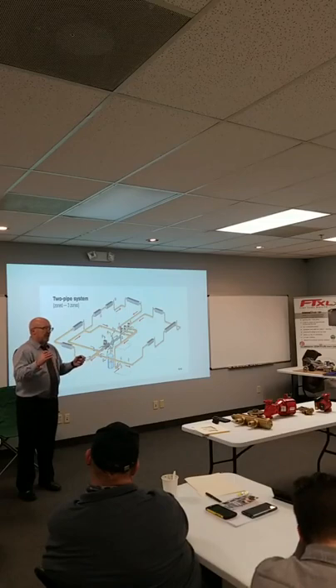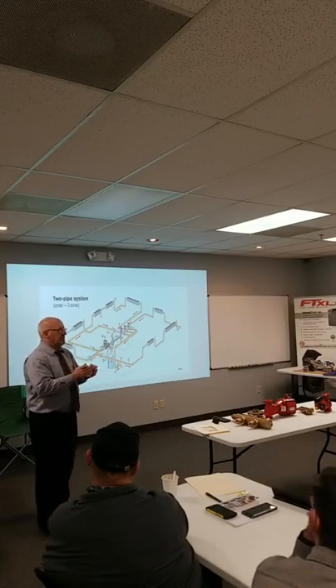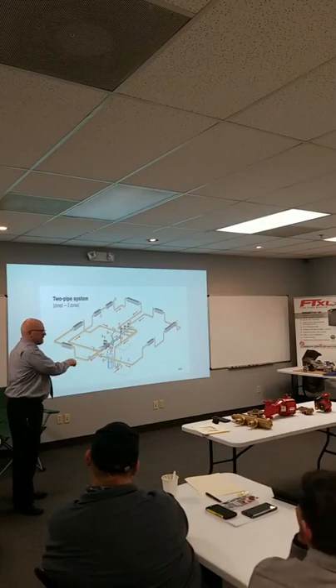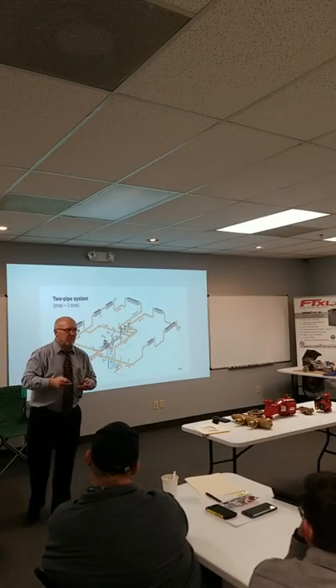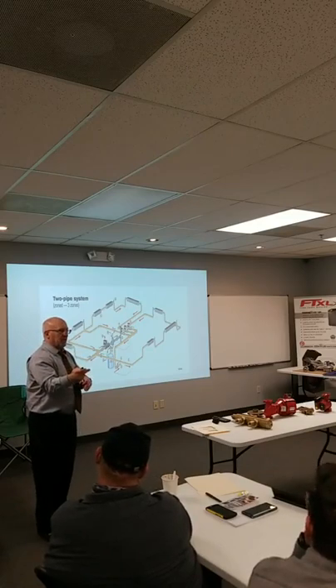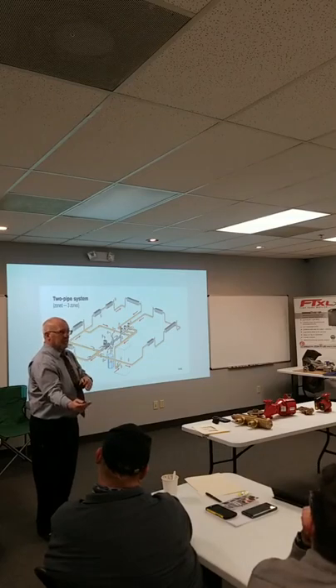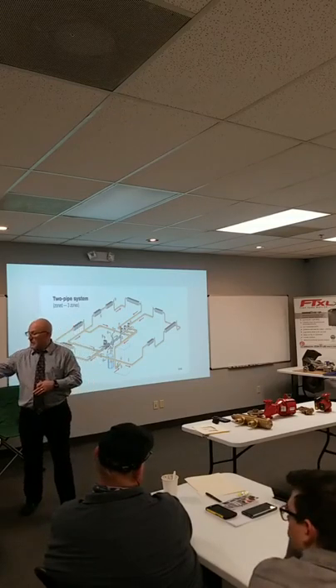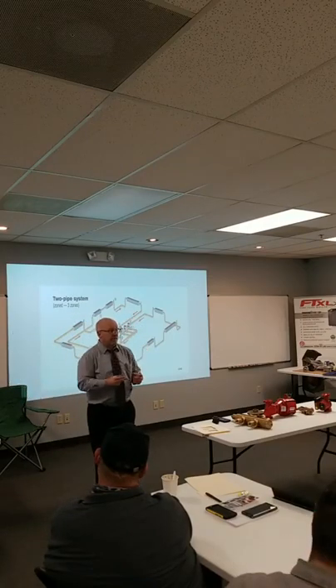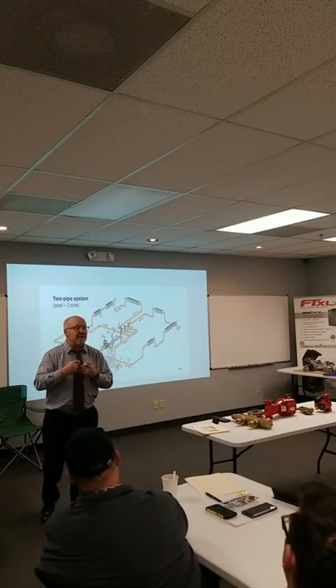And when we use the pump head to increase pressure into the system, we collapse air bubbles. And the idea of getting the air bubble back through the system and back to the air separator is what we're trying to do. Okay, so we collapse it. If we're lowering the pressure, not only does air come out of solution when we heat it, but also when we drop in pressure. When we open up that Diet Coke bottle, what happens? We're lowering the pressure, right? And then all those bubbles start coming out of the pop. That's the same principle. We remove air when we lower pressure.